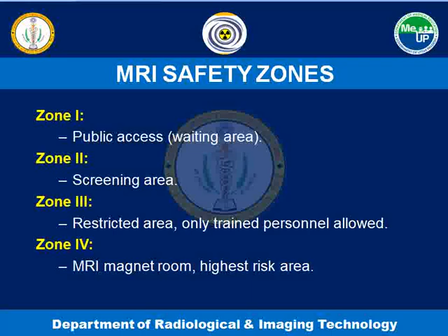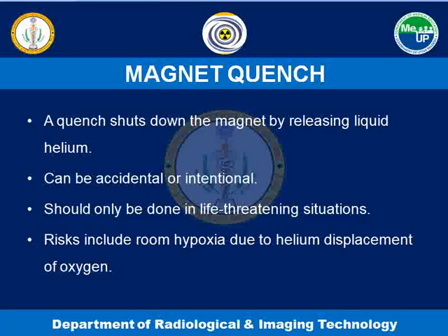Next, magnet quench. A quench shuts down the magnet by releasing liquid helium. Can be accidental or intentional. It should only be done in life-threatening situations. Risks include room hypoxia due to helium displacement of oxygen.